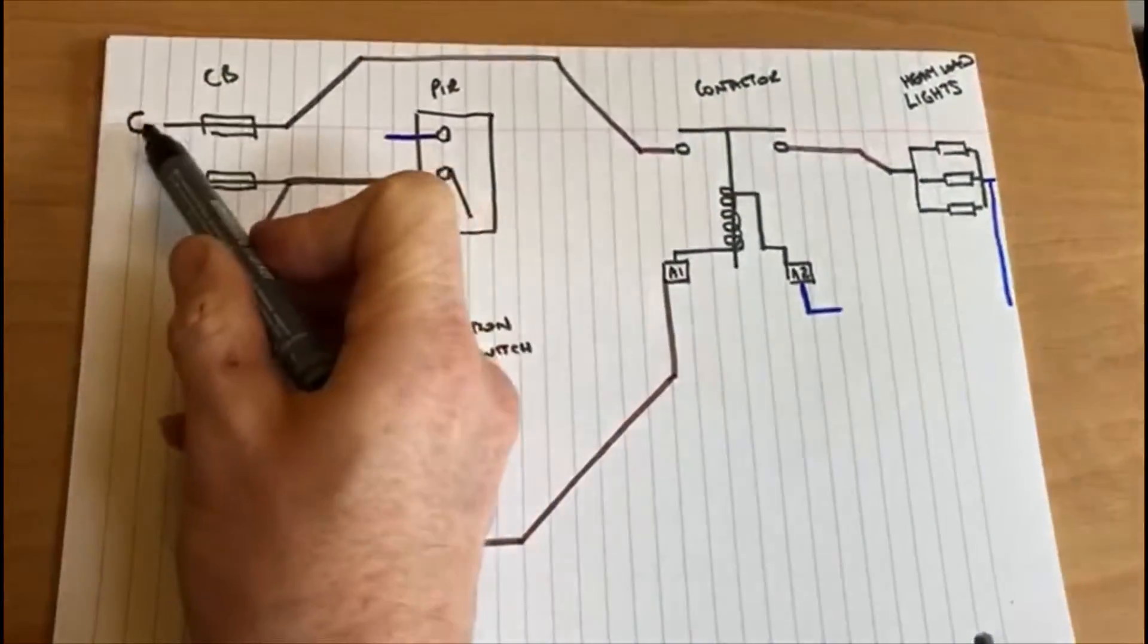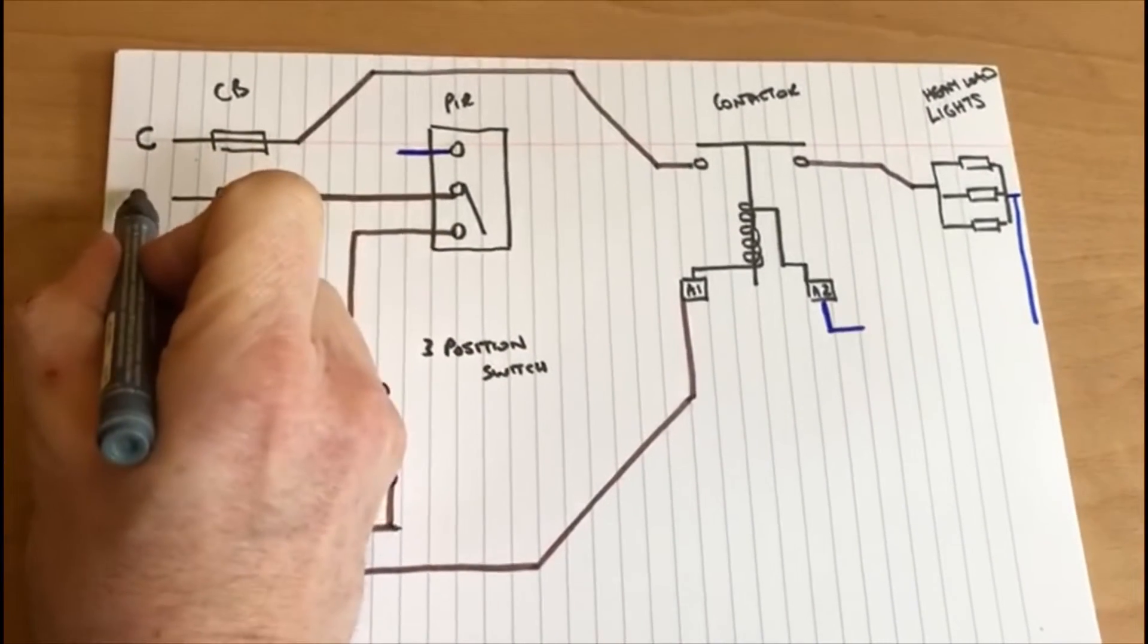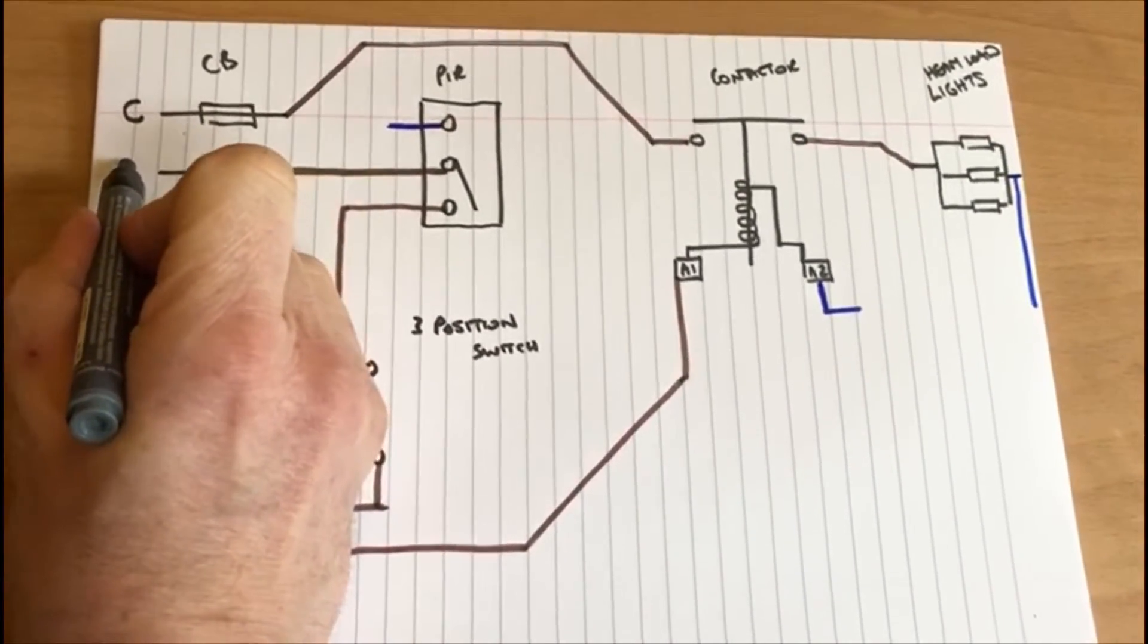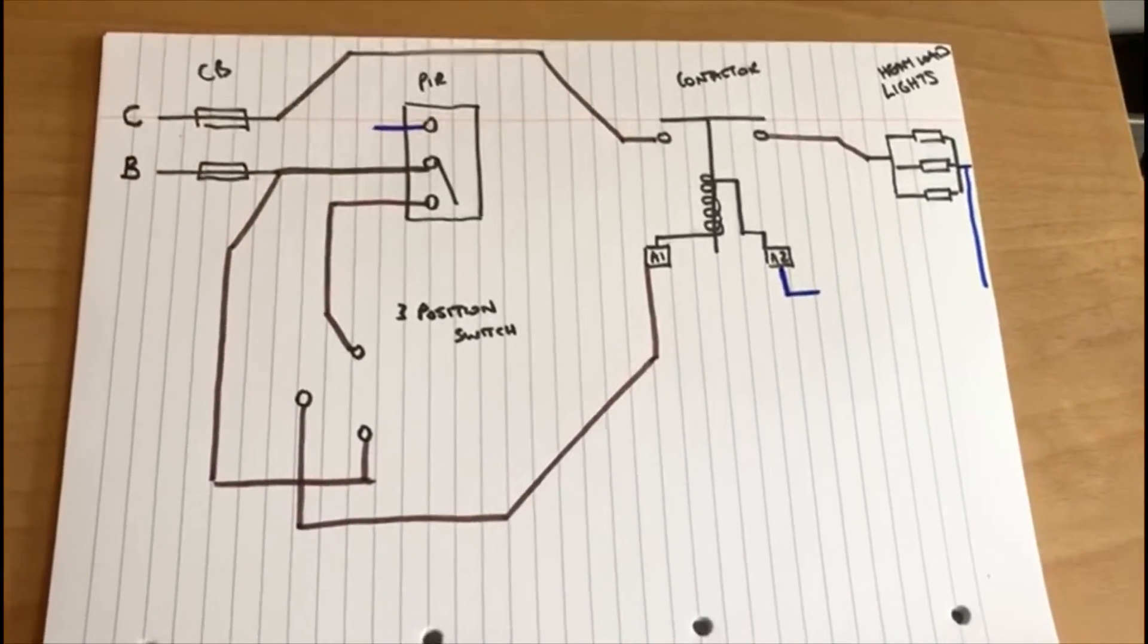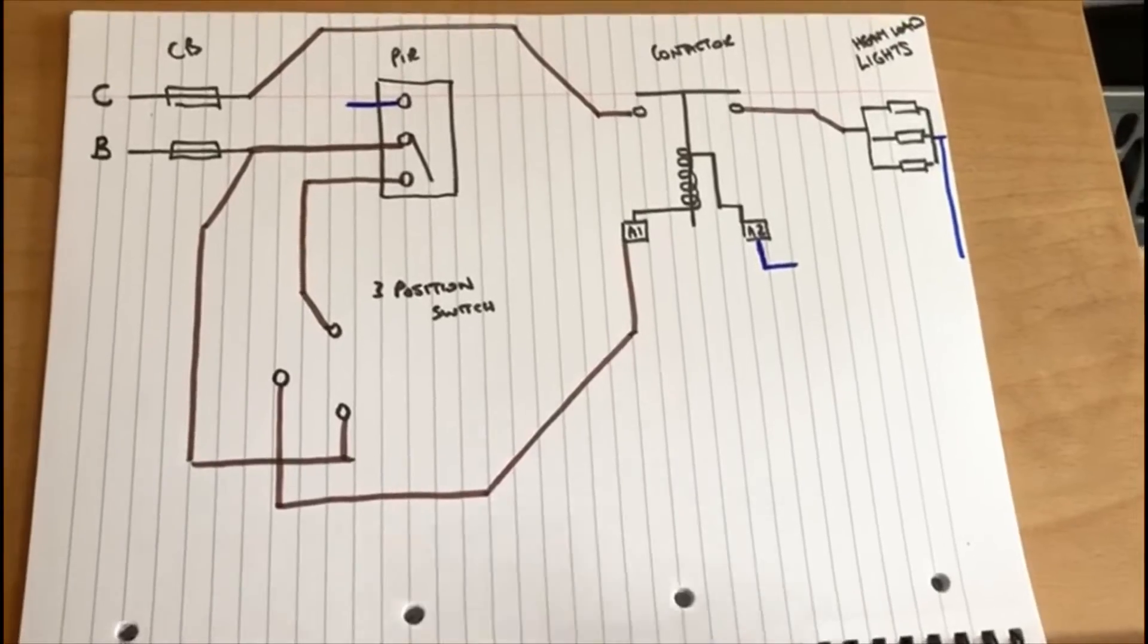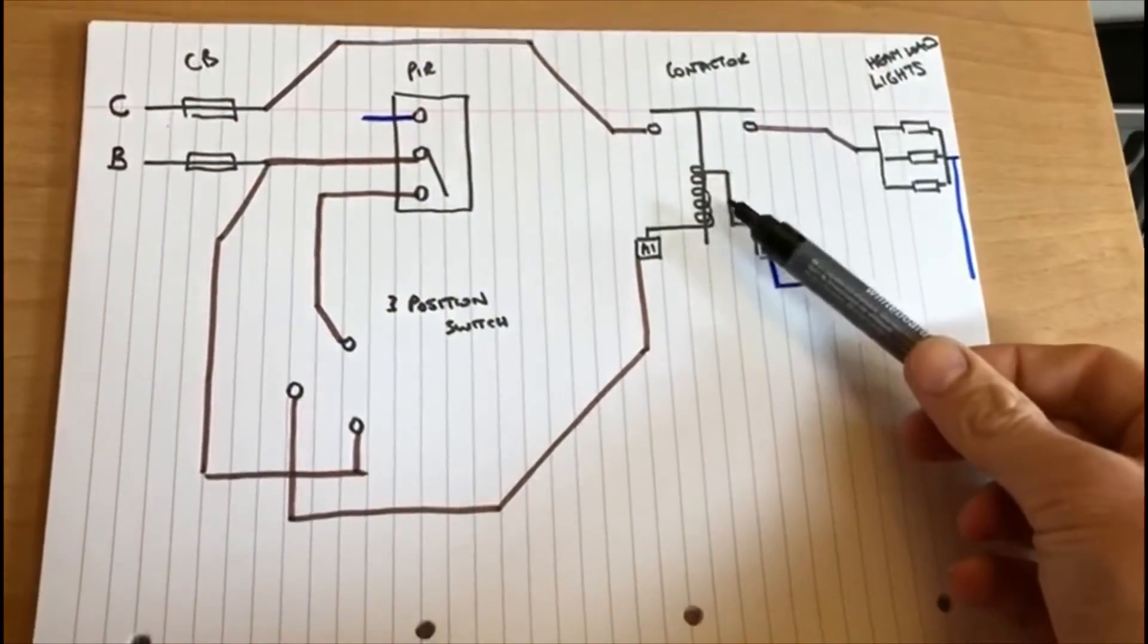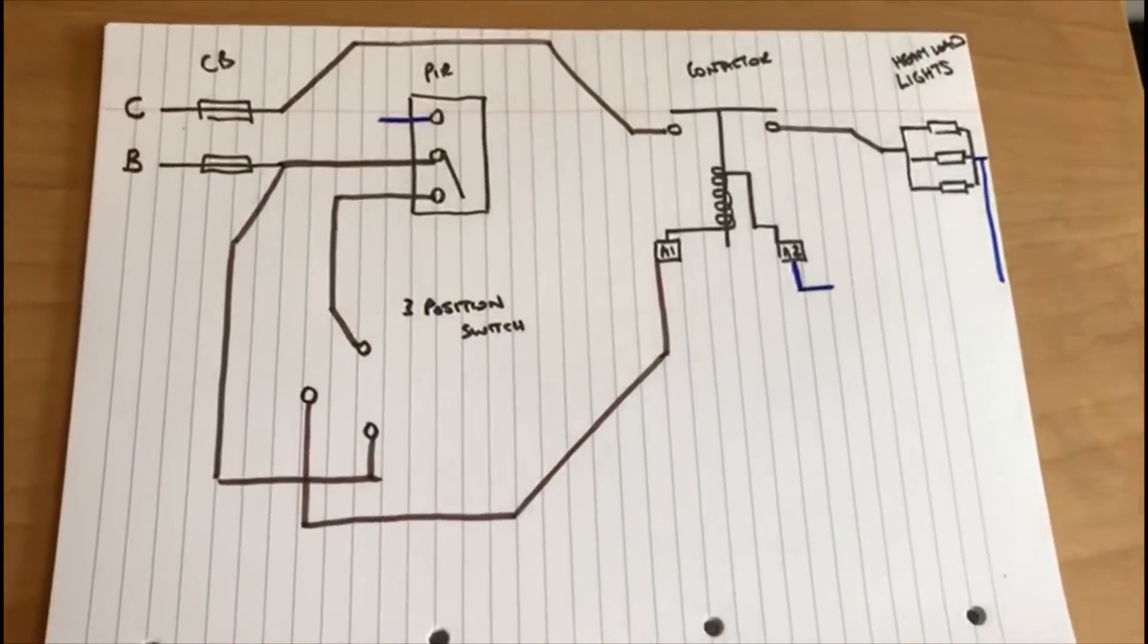So C type breaker might be important. This one however is just operating the coil of the contactor, so this only needs to be a small B type circuit breaker. So for example if that was drawing 15-20 amps, you'll probably have a 20 amp contactor and maybe a 20 amp circuit breaker here.